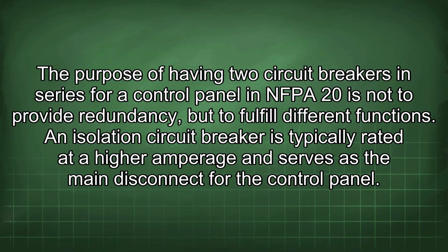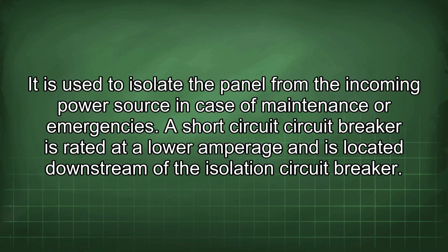The purpose of having two circuit breakers in series for a control panel in NFPA 20 is not to provide redundancy, but to fulfill different functions. An isolation circuit breaker is typically rated at a higher amperage and serves as the main disconnect for the control panel. It is used to isolate the panel from the incoming power source in case of maintenance or emergencies.